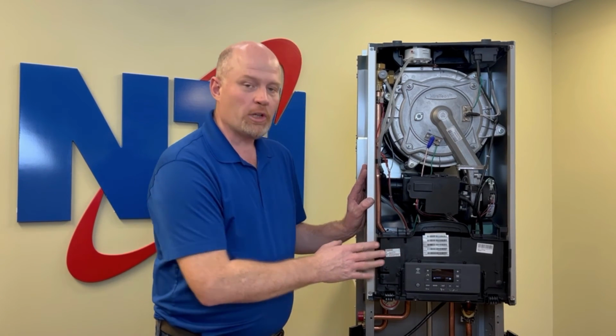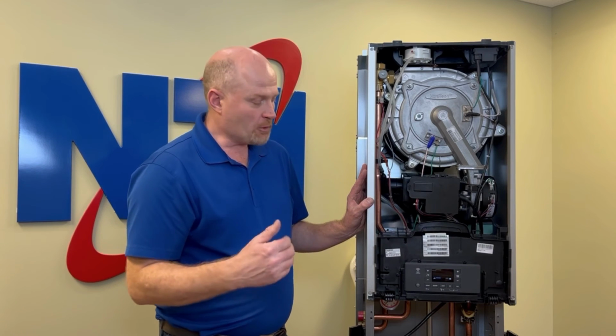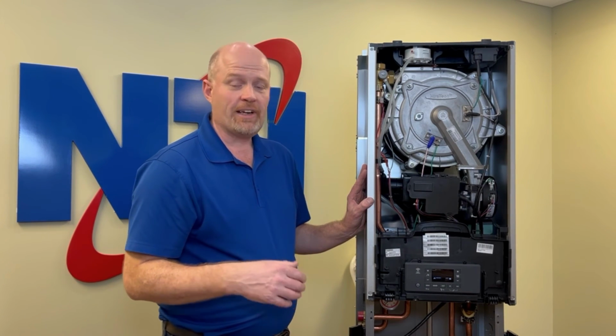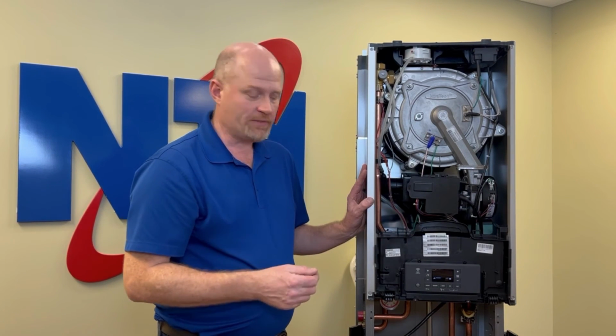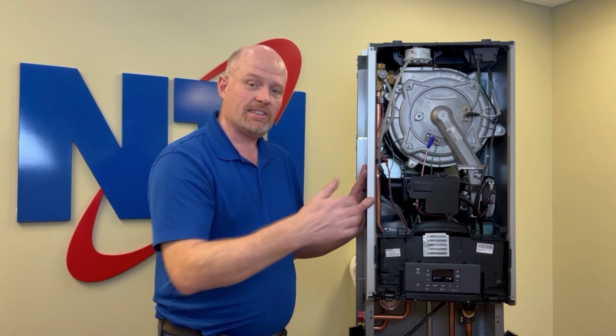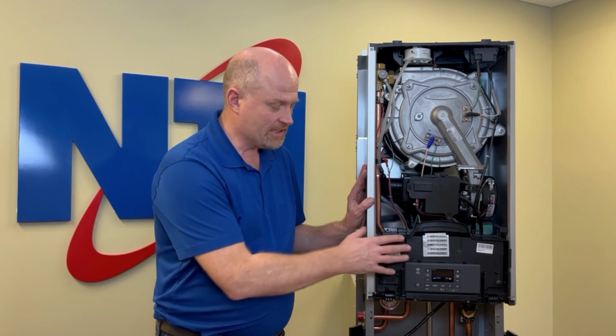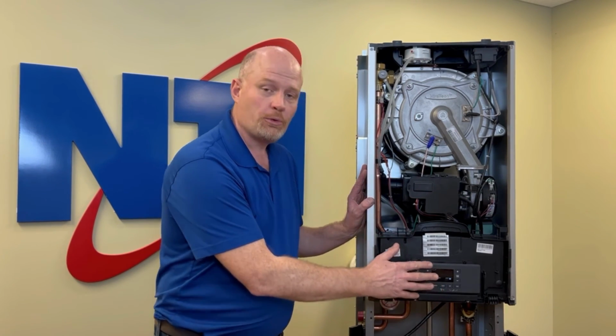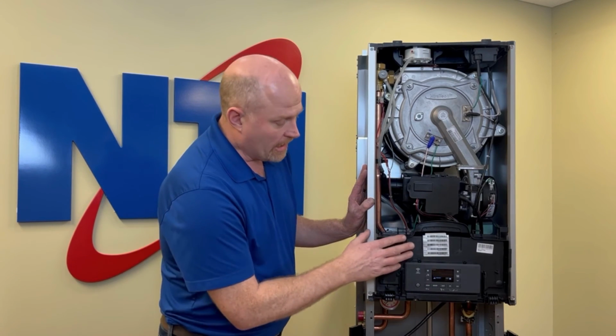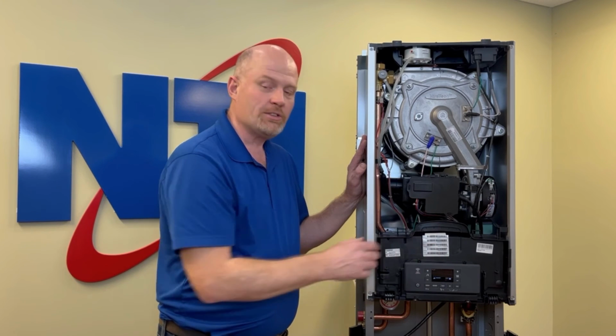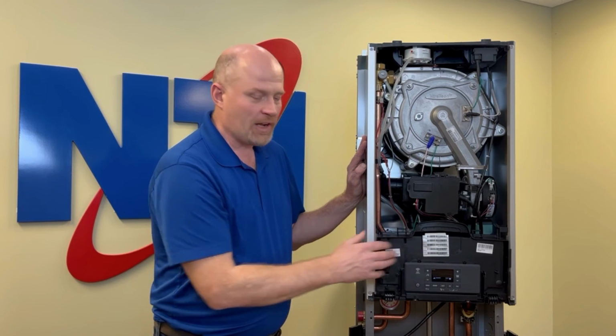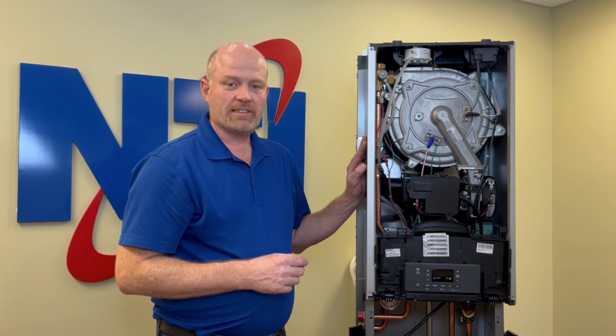A reading that the boiler will accept is anything from a temperature around 30 degrees Fahrenheit all the way up to 200 degrees Fahrenheit. Any of the resistances in that range are going to be acceptable to the boiler, and error code 203 should not be displayed. If you have a resistance reading in between those two values and the boiler still does not recognize it, then you would have a bad circuit board and would want to replace that.